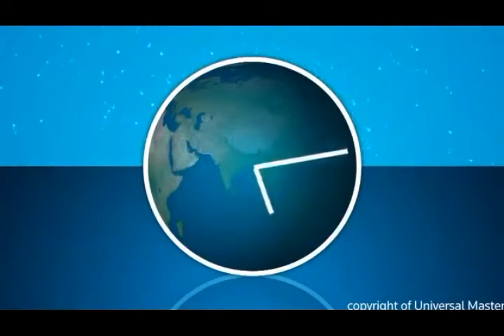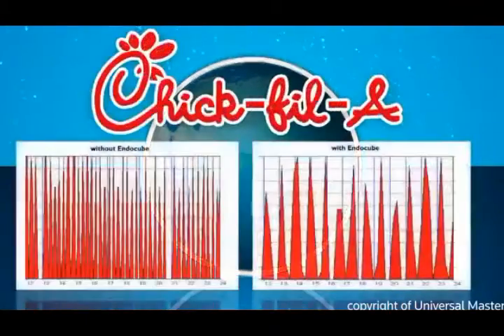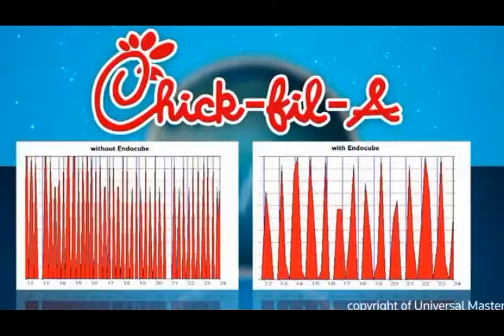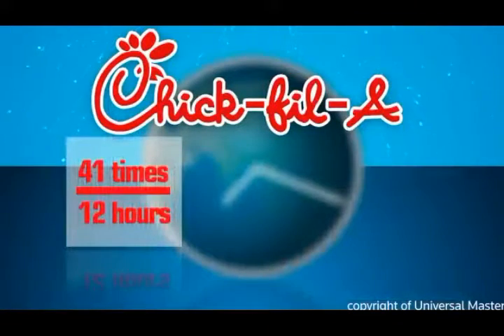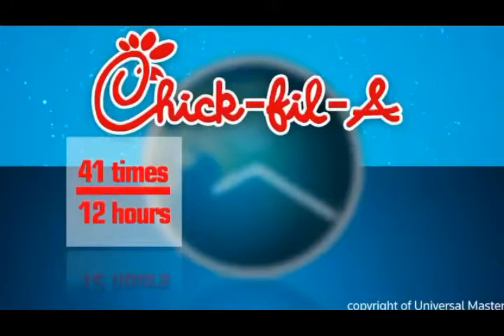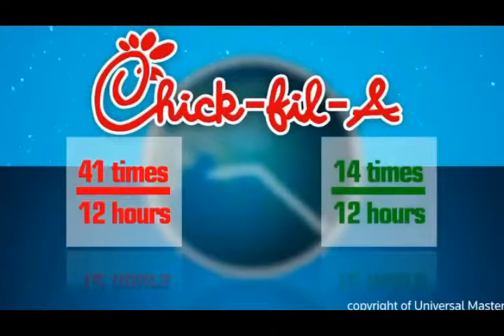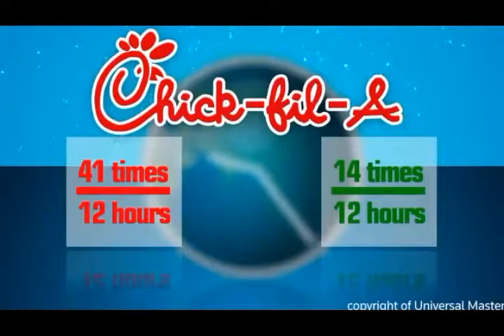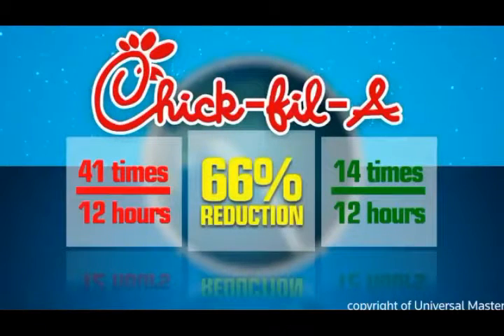Look at this recent case study from a walk-in refrigerator at a Chick-fil-A. Without Endocube, the compressor cycled 41 times in a 12-hour period. With Endocube, it cycled 14 times in a 12-hour period. That's a 66% reduction in compressor cycles after the installation of Endocube.